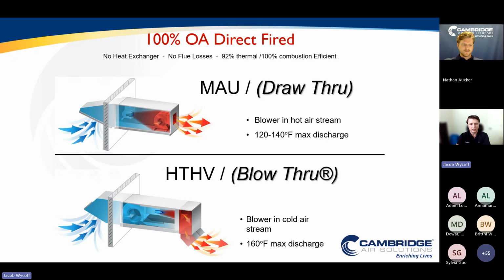So what HTHV units do is they actually flip where the burner and the blower are in the airstream. So the blower is moved upstream of the burner into the cold airstream. And what that does is it allows HTHV units to discharge at a much higher discharge temperature reliably and consistently year-round. So when you put that blower up in the cold airstream, that's going to have huge impacts on the ability to heat the space efficiently whenever you no longer have that restriction on discharge temperature. And we'll go through why that is later in a few slides.